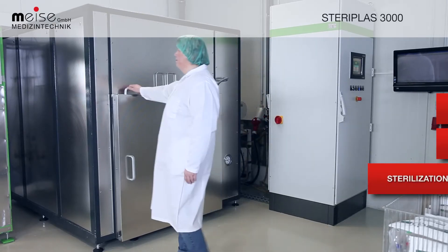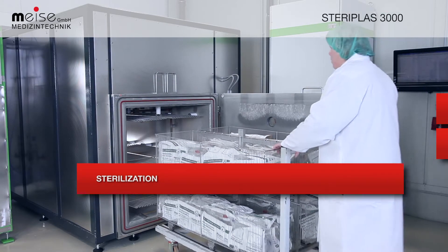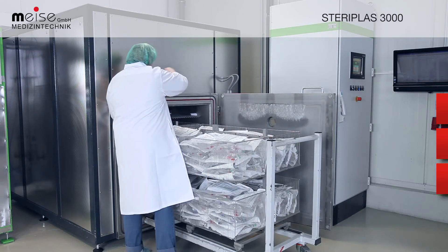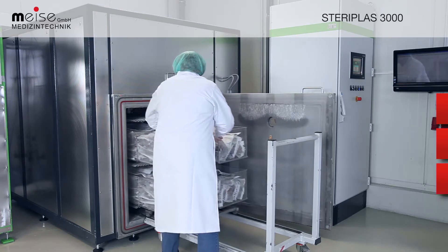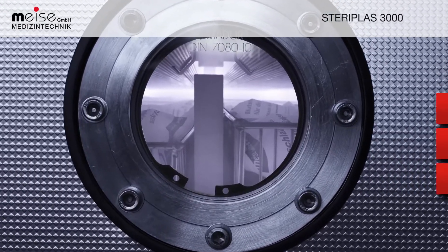Gentle and economical sterilization — this is what Meise uses the SteriPlas 3000 for, which is currently the world's largest gas plasma sterilizer. It has a vacuum chamber volume of 3000 liters, which makes it highly efficient economically too. H2O2 is used for its gentle sterilization procedure. For cleansing purposes, the remaining gas is made to pass over into the plasma state through high-frequency voltage.